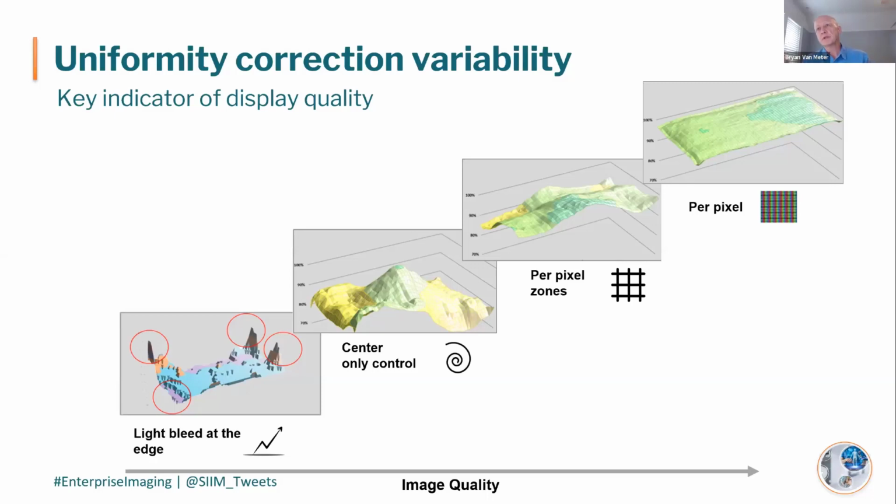Our pathology display is a higher end display, but it has to do with pixel management. This is a display algorithm. Think of pixels of a display that are broken up into individual zones on the horizontal axis and the vertical axis. Those individual pixel zones communicate with each other and explain to each other what's going on, so they modulate out and manage that uniformity.